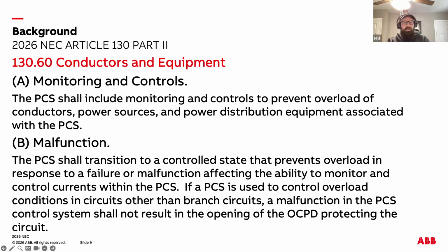When monitored values approach the allowable threshold, the PCS must act quickly enough to prevent an overload. This may include shedding loads, throttling loads, limiting DER output, or staggering loads. The timing requirement ensures PCS can serve as a safety-critical system. The system must operate with sufficient accuracy to ensure that its control decisions are based on correct measurements. Reliability expectations include stable operation under normal and abnormal conditions, predictable behavior during transitions, and no unsafe oscillations or rapid cycling. We call them thrashing, and that's outside the conditions of the listing.